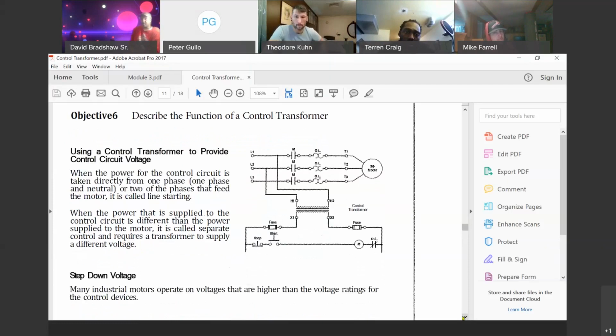Let's go back up. When the power for the control circuit is taken directly from one phase, meaning L1 to neutral, L2 to neutral, or L3 to neutral, we can use that to give us 120 volts across the circuit, but we don't want to do that because that's not the way this transformer theory works, okay? So when they talk about the power supplied to the control circuit being different than the power supplied to the motor, it is called a separate control and requires a transformer to supply a different voltage.